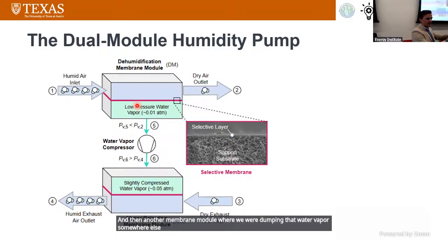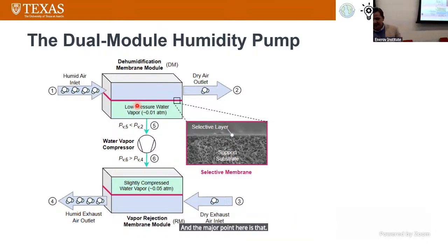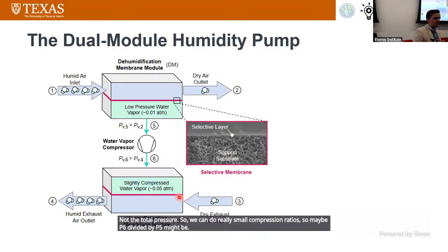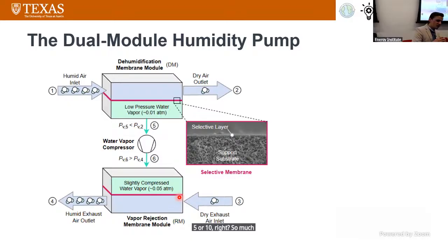We could be dumping it to the outside, or to some sort of exhaust air—it doesn't really matter. The major point is that as long as the pressure at state 6 is greater than the water vapor partial pressure of the air flowing on the opposite side of the membrane, what drives mass transport is the difference in water vapor partial pressure, not the total pressure. So we can use really small compression ratios—maybe P6 divided by P5 might be 5 or 10, a much smaller increase in pressure.